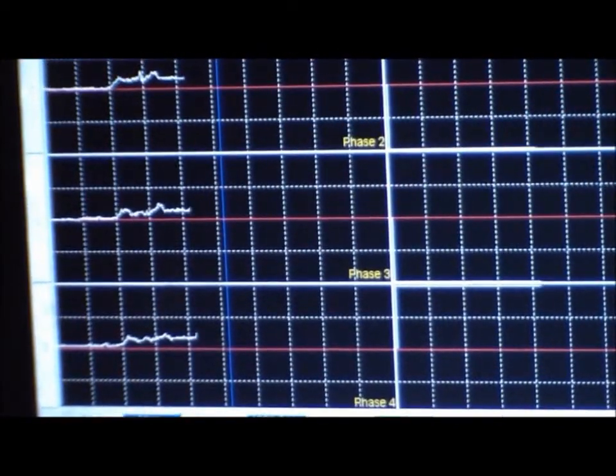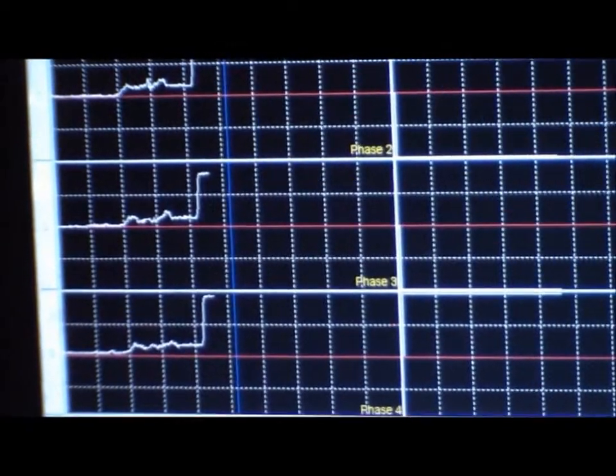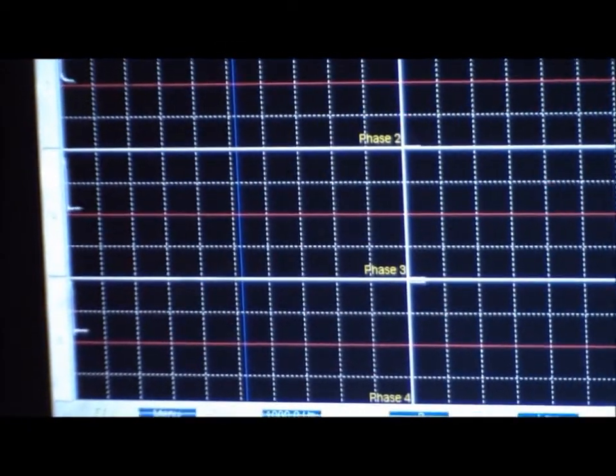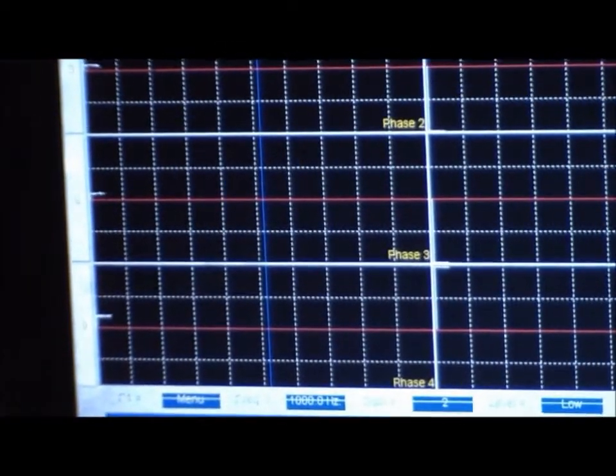The principles of LFET function by injecting an electromagnetic signal into the test piece, and this signal is measured while the scanner is moved across the tube.